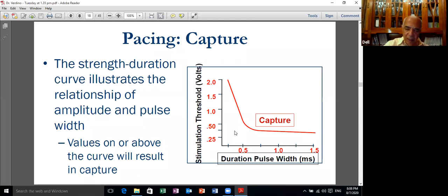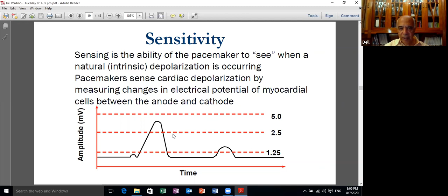Now we move from capturing to sensitivity. It's a programmable function of the pacemaker. Sensitivity is the ability of the device to see the different complexes. We like the device to see the QRS and not to see the P wave or the T wave. If you program the device to be very sensitive, so that the sensitivity value is low here, then it's going to sense everything. It will sense the T wave as well as the QRS complex, and the pacemaker does not distinguish between them, so it's going to double count the heart rate. But if you put the threshold at a higher number, that's a low sensitivity, it's not going to sense anything. So we put it here in the middle, something like 2.5 millivolts. Under these circumstances, it will not sense the T wave, but it will sense the QRS.